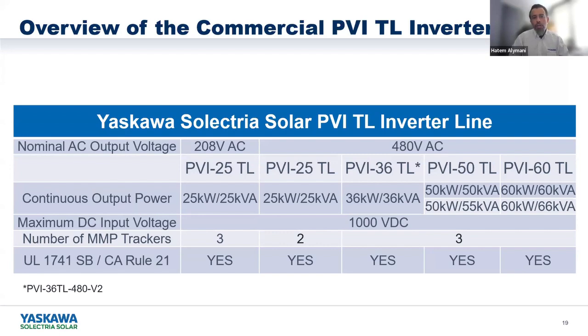All these inverters, of course, they are UL 1741 SA certified and California Rule 21 listed as well. And they have all those smart grid features that the utility might ask for, and all the information about how to control the inverter, about how to derate the inverter. For example, if the utility will need a derating later, we can offer that as well. And all this information, you'll find it in our installation manual. Our installation manual for those inverters basically covers all the information. And there is an additional Modbus map if you need to communicate with those inverters remotely through a third-party monitoring system or a DAS.